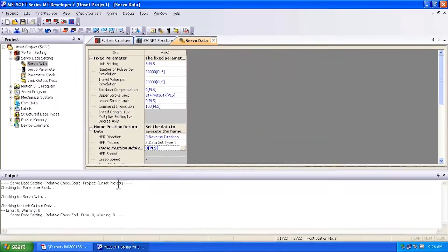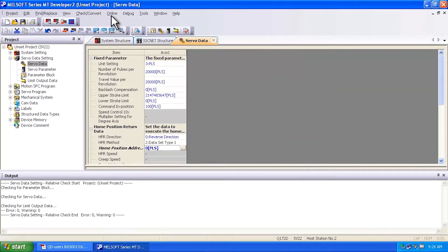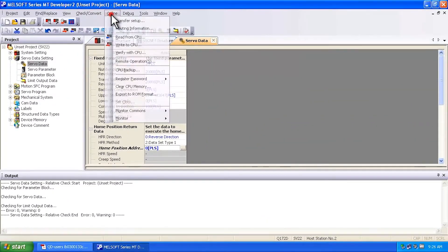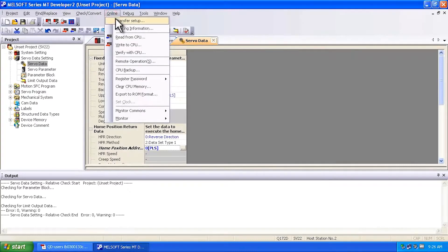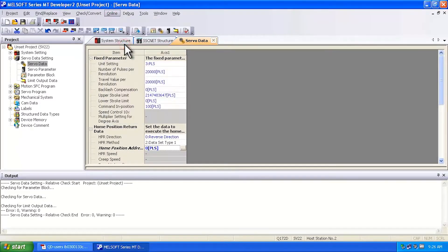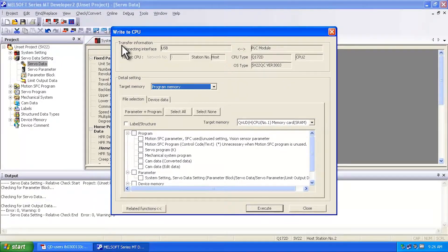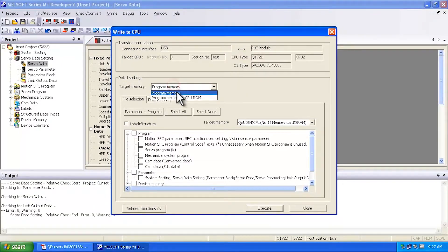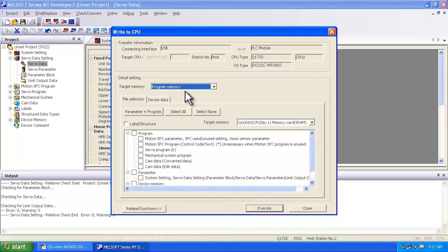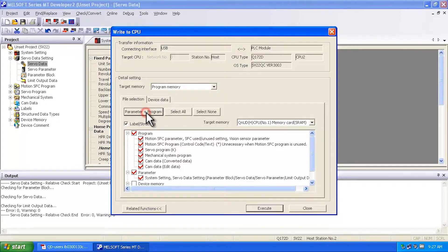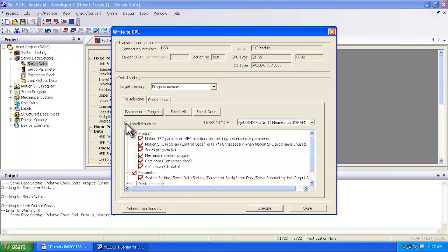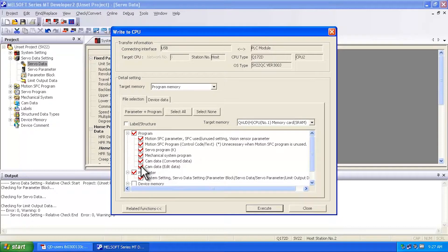Okay, now the next thing you're going to want to do is write to your controller. So I go to write to CPU and I'm going to get a screen that then allows me to write. Now, when you specify program memory, it's a good idea to click the parameter program button, but keep in mind the label structures require a memory card.